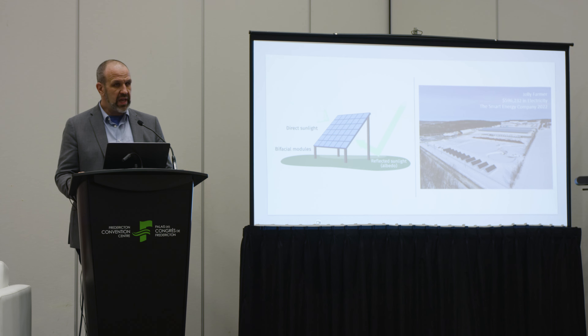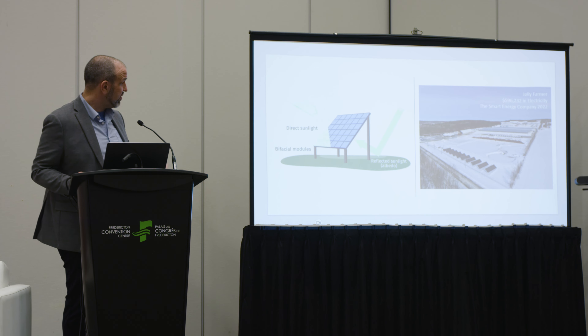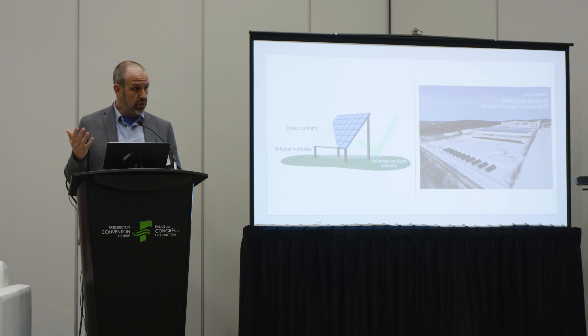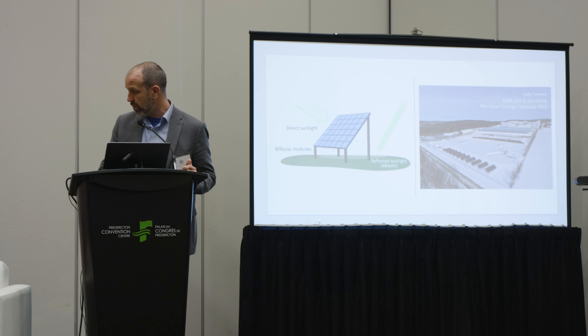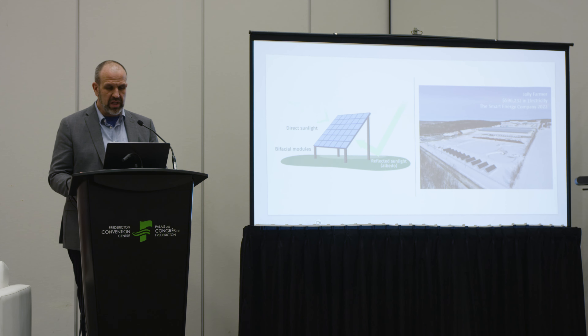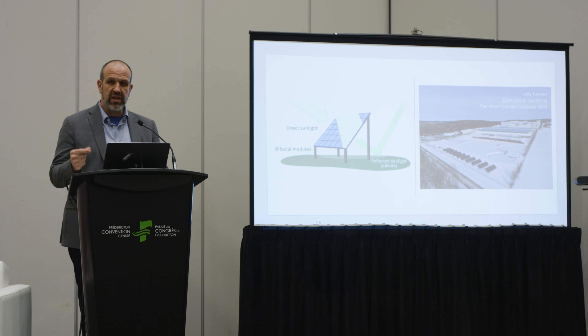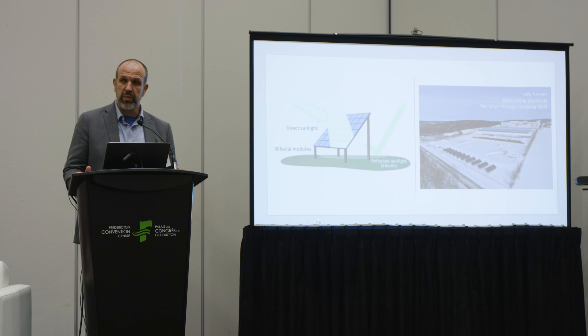More importantly, it's about snow. When we put solar panels on the ground, we use bifacial solar panels — they're double-sided and produce on both the front and the back. What's special is that overnight if there's wet sticky snow accumulating on the front, as soon as the sun comes up it reflects on the ground, hits the back of the solar panel, and creates about 8% to 10% more electricity. But most importantly, it warms the front — it's almost like the panels are in a defrost mode. By 9:30 to quarter to 10, the snow sloughs off. That is the most important reason we put solar panels on the ground — we can confidently predict how much electricity it's going to generate, and you're not actually buying a solar farm, you're buying electricity.